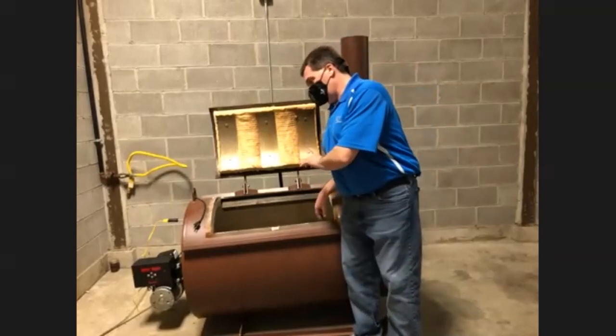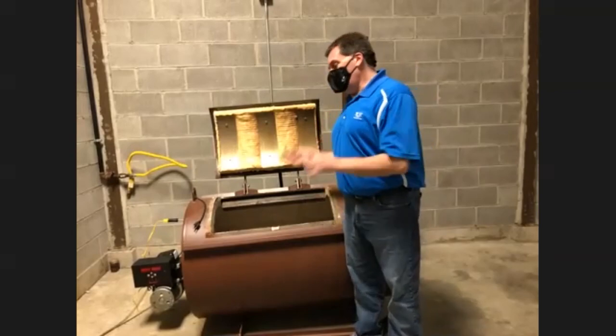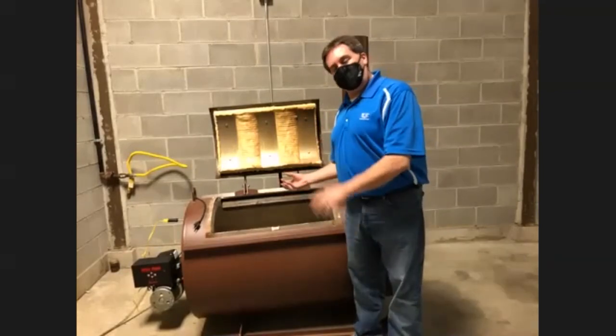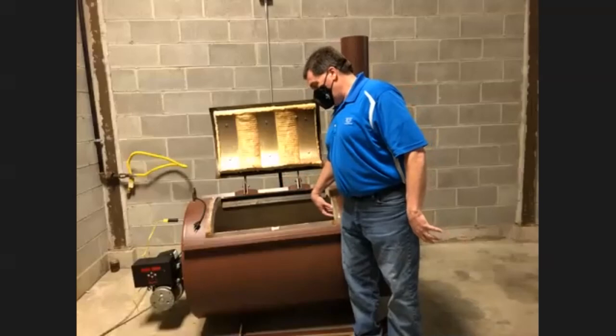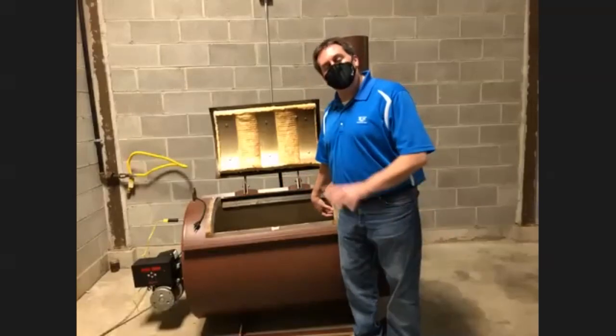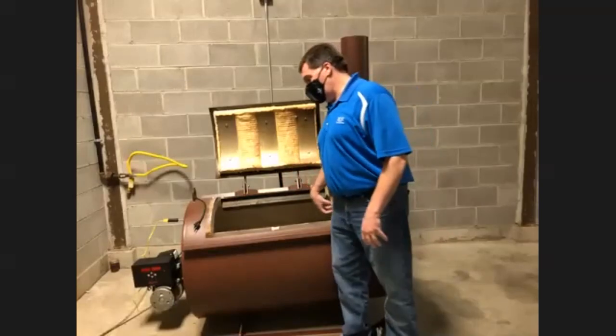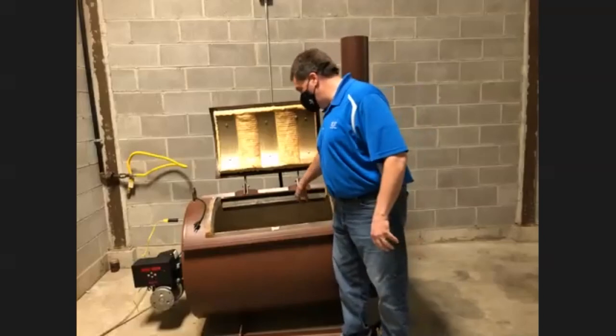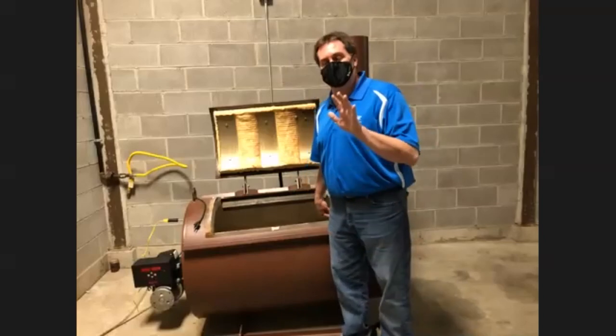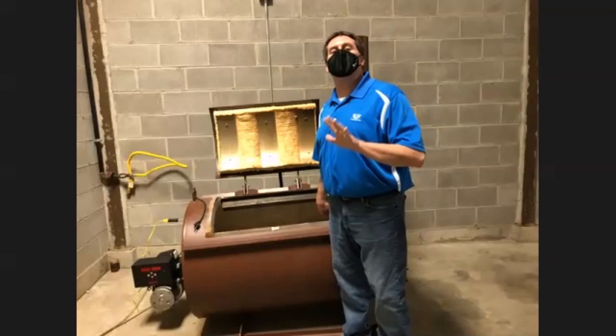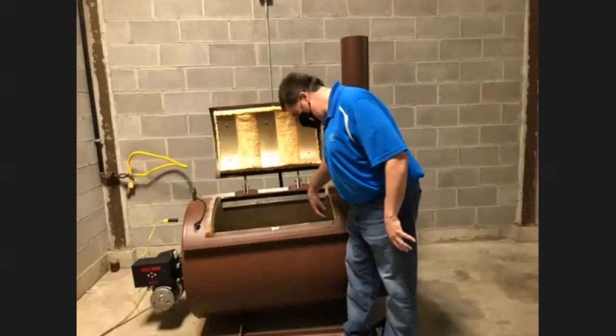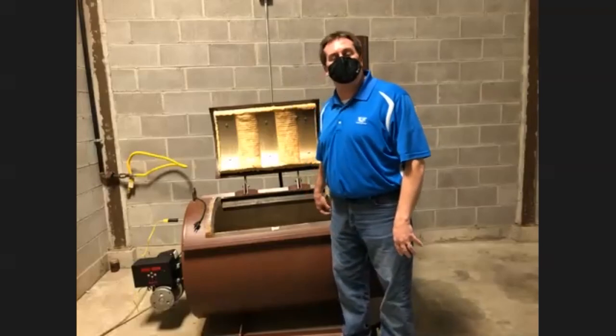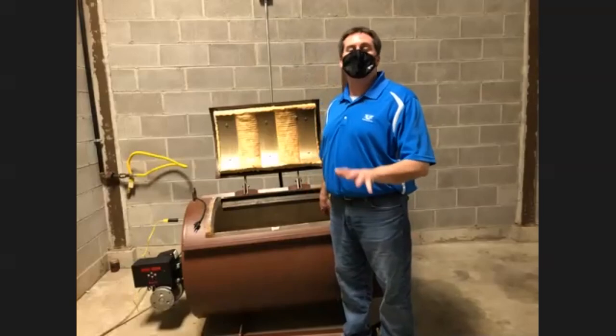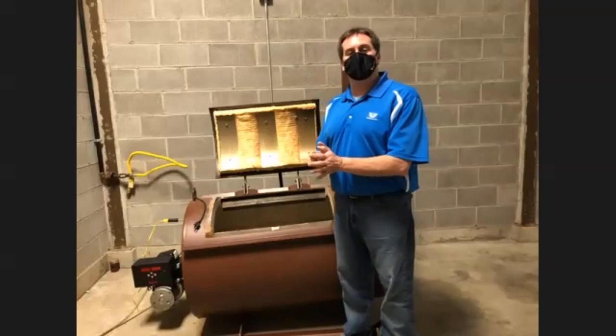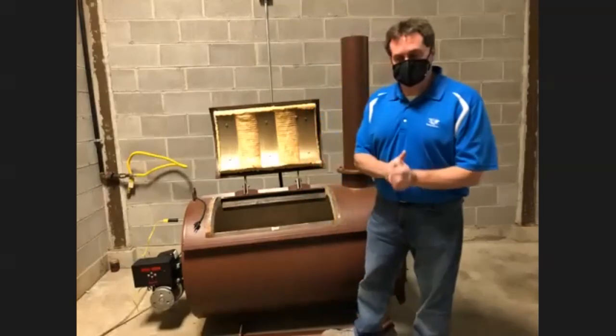And with this, I just remembered, when you first operate these units, the refractory is cured to a point, but when you start operating them, they'll continue to cure a little bit more. You may see cracks in them. That is normal. That is not uncommon. That is a very normal procedure; they are curing. You may generate small cracks. There's nothing wrong with that. They will still hold their shape and do their job properly.